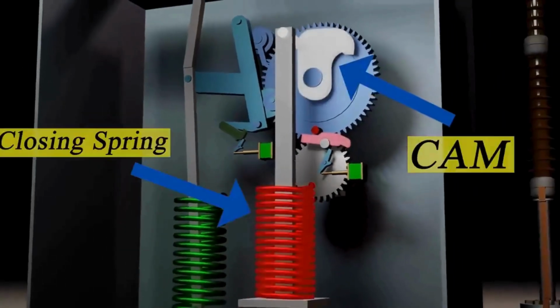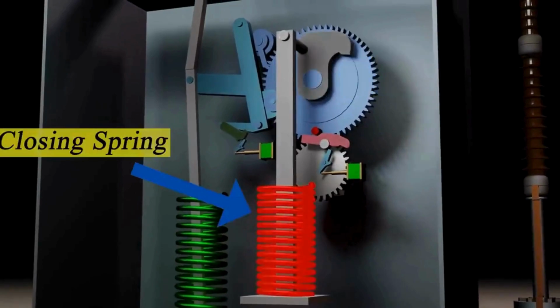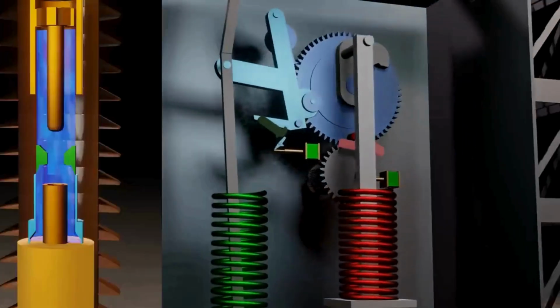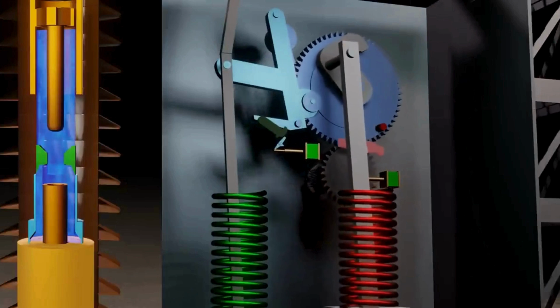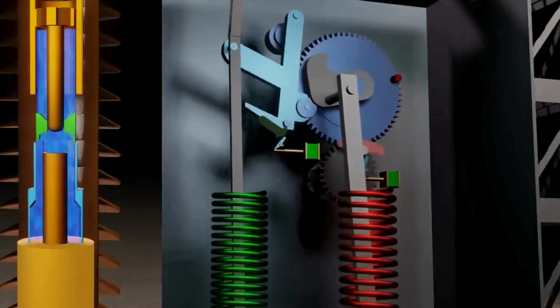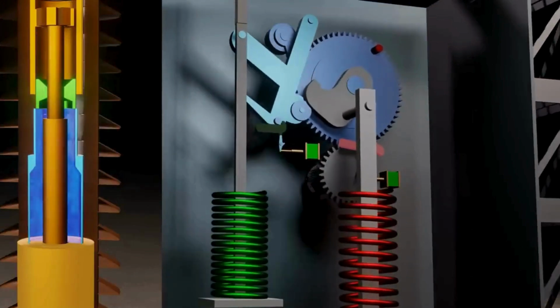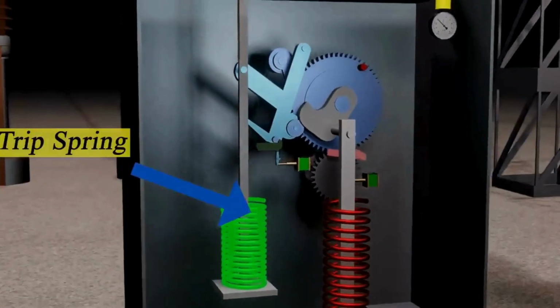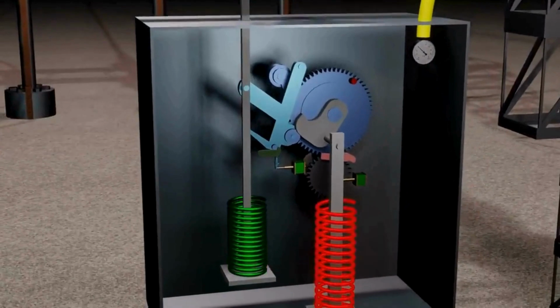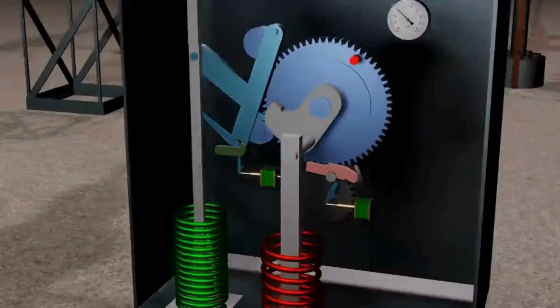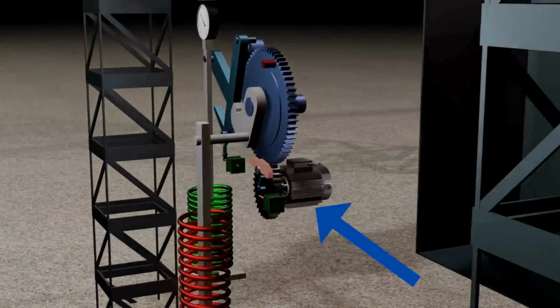The spring that trips the line can only be charged by the closing spring, and there is a motor on the side to charge the closing spring. Then the spring will start loading again as soon as the circuit breaker closes. The opening and closing time of these circuit breakers is only 40 to 60 milliseconds.